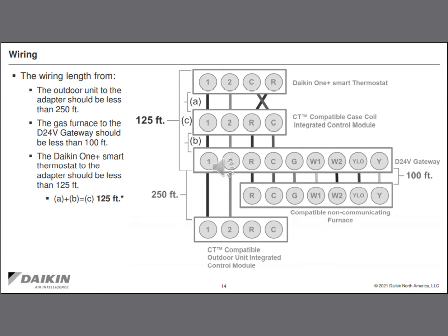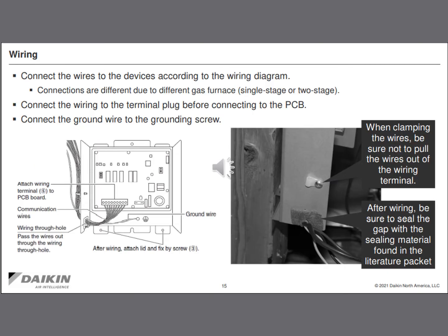From the gateway, then we will interface with 24 volts to our non-communicating furnace. And then, of course, from the gateway, we're going to take 1 and 2 out to our outdoor unit. Once we make our wiring connections to the gateway adapter, we're going to make sure we have a ground wire on there as well. Make sure that we have a ground wire that connects this to the chassis ground of our unit. And then also make sure that we seal up that hole where our control wiring went through there. That'll prevent condensation and other issues that we have with air traveling through there.